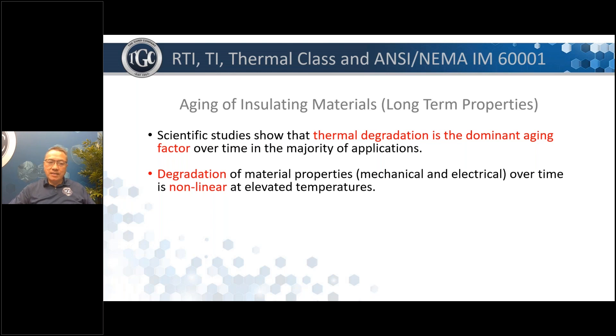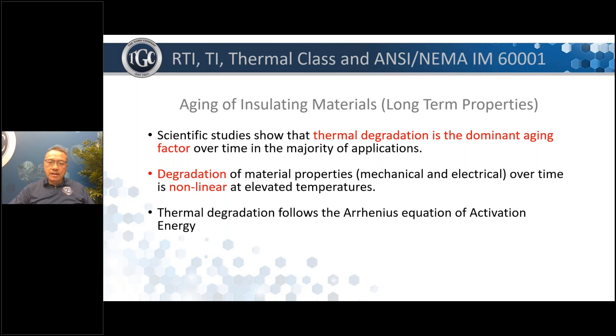What that means is that at the beginning, at a certain elevated temperature, the degradation is slow and then it accelerates — not in a linear manner. With UL long-term thermal aging for materials, covered under UL 746B, the mechanical properties tested are tensile and, if the material is thick enough, impact as well. The electrical property tested is always dielectric strength.